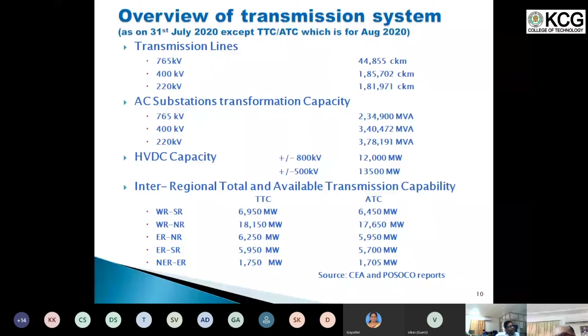Typically, you will see that a large interregional transmission capacity figure is quoted, but there is a fallacy there: that capacity is the capacity of each element all added together arithmetically. In an integrated system, that doesn't happen. When you have several connections between two regions, power will not flow equally on all those links in proportion to their capacity, but as per the network parameters.